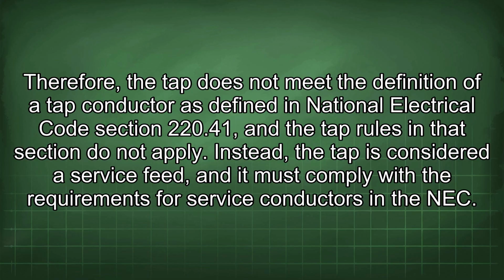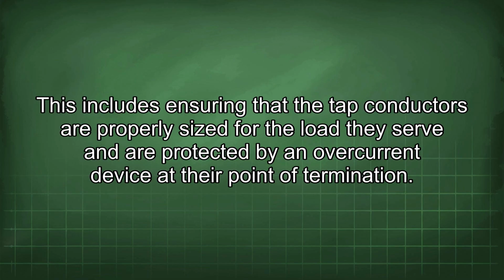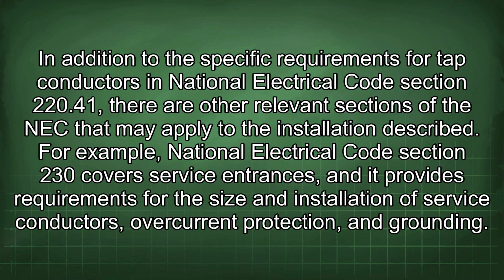Instead, the tap is considered a service feed, and it must comply with the requirements for service conductors in the NEC. This includes ensuring that the tap conductors are properly sized for the load they serve and are protected by an overcurrent device at their point of termination. In addition to the specific requirements for tap conductors in National Electrical Code section 220.41, there are other relevant sections of the NEC that may apply to the installation described.